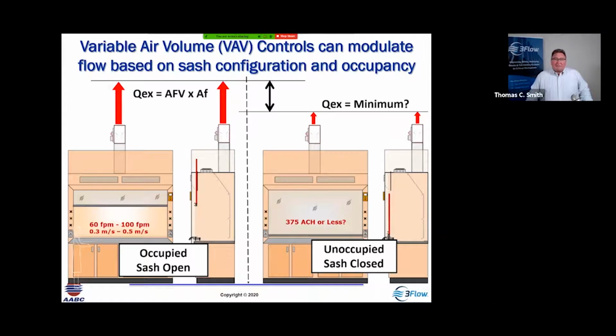Of course, as balancers, we would do a pitot traverse in the exhaust duct and confirm it. But what if we can't? How do we look inside the hood and determine the minimum flow through that fume hood opening from in front of the hood? And then how do we calibrate the monitors? We need to make sure that we've got a good calibration in order to get reliable data, and that information is going to be shared with the building automation system. So the accuracy and precision of our measurements here are very critical because they drive the operation of the system.